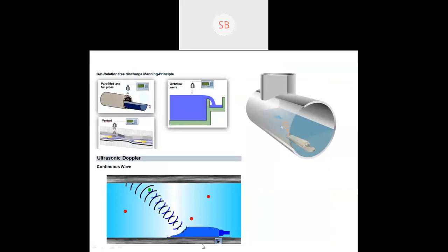If you are able to fix it at the bottom of the canal or the profile, it could get the water speed at different layers altogether. The good resolution instrument available from Sontek could give 128 samples or layers. It picks up the velocity at 128 layers from the top to the sensor line. At every point, it makes a velocity approximation by which it could calculate the discharge, provided the cross-section is given into the calculations. It can go in a closed pipeline also. This works in an open channel as well as in a closed pipe.